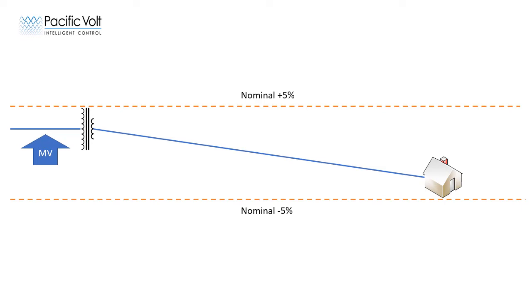Because there are millions of secondary circuits in North America, there is a strong economic pressure to reduce their cost, meaning smaller transformers and conductors which have higher impedance. Traditionally, the system was designed so that the voltage on the medium voltage feeder was kept high enough to accommodate for the voltage drop on these secondaries. This strategy worked well until rooftop solar came along and complicated things.